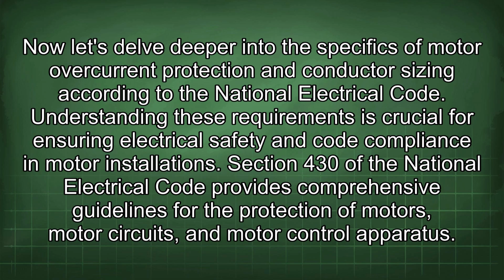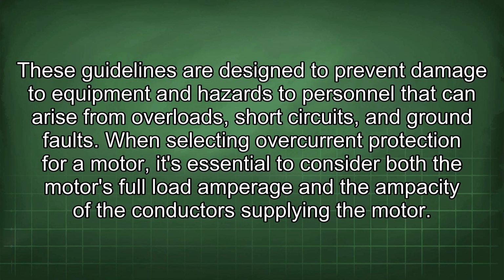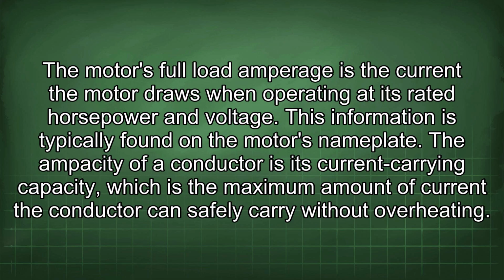Section 430 of the National Electrical Code provides comprehensive guidelines for the protection of motors, motor circuits, and motor control apparatus. These guidelines are designed to prevent damage to equipment and hazards to personnel that can arise from overloads, short circuits, and ground faults. When selecting overcurrent protection for a motor, it's essential to consider both the motor's full load amperage and the ampacity of the conductors supplying the motor. The motor's full load amperage is the current the motor draws when operating at its rated horsepower and voltage. This information is typically found on the motor's nameplate.